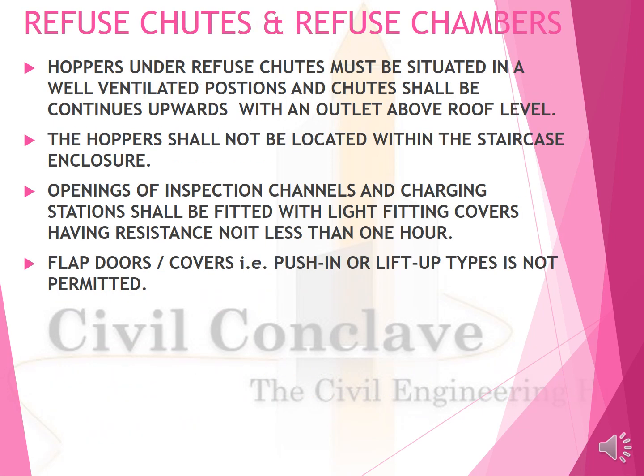Refuse chutes and refuse chambers. Hopper under refuse chutes must be situated in a well ventilated position, and the chute shall be continued upward with an outlet above roof level. The hopper should not be located within the staircase enclosure. Opening of inspection channel and charging station shall be fitted with light fitting covers having a resistance not less than 1 hour. Flap doors, that is push in or lift up types, are not permitted.